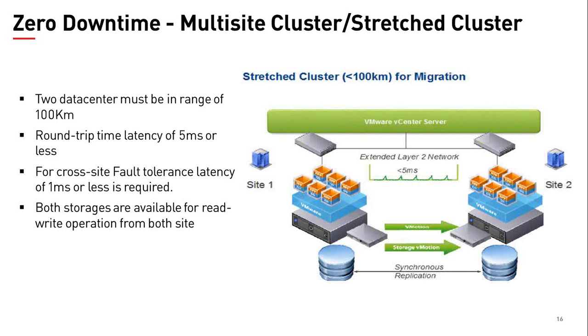Data centers purely in active mode. You need to ensure that both the data centers are within a range of 100 kilometers. Latency should not be beyond 5 milliseconds.